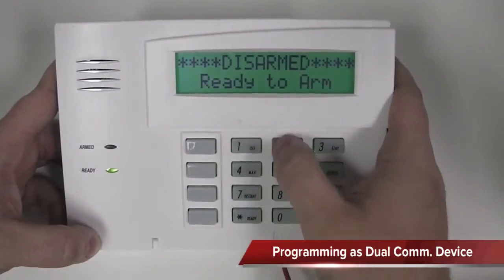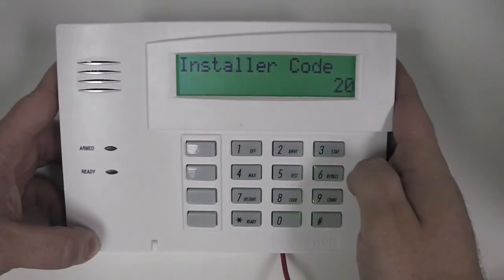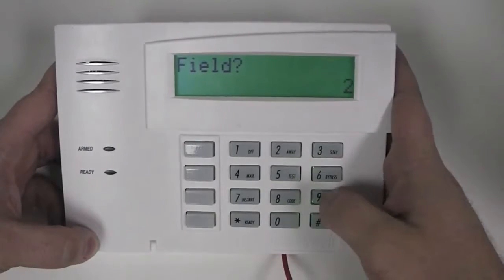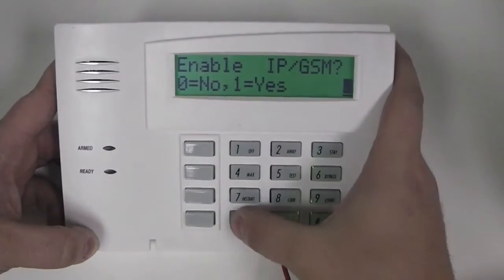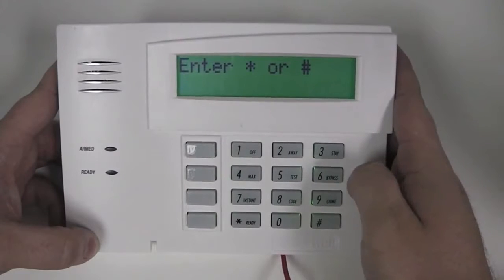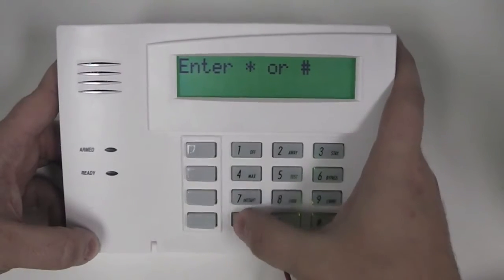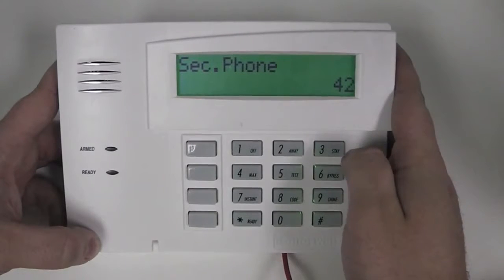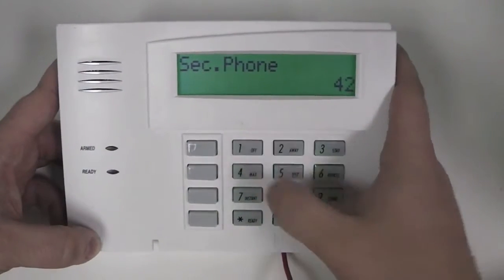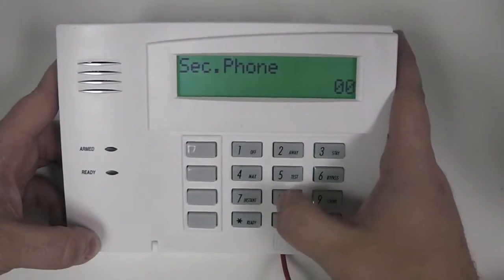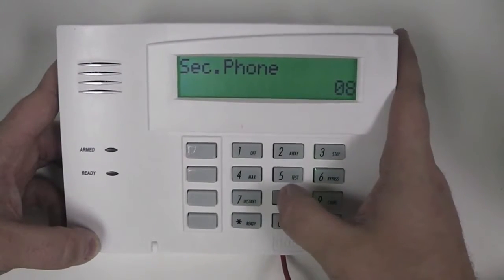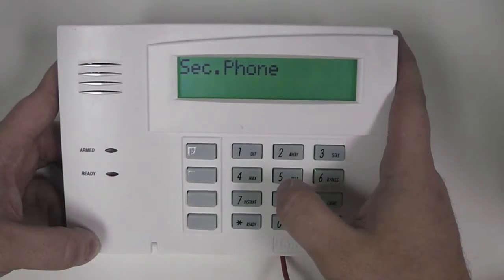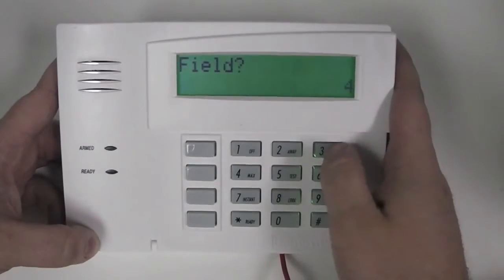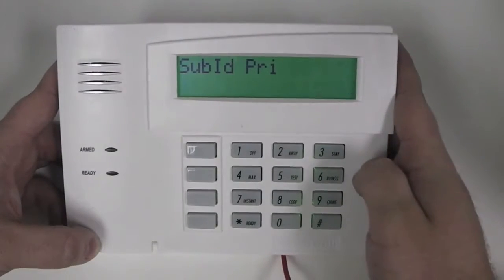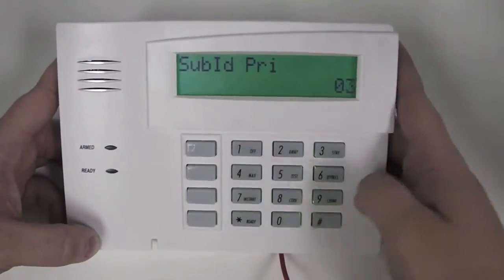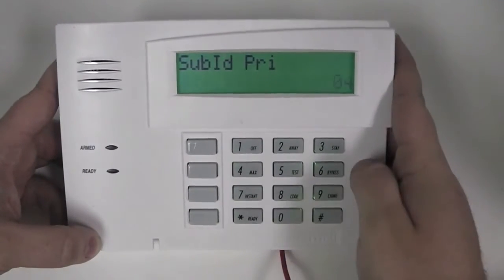The last way to program the BAT is as a dual communicator. You start off by entering programming again, and then verify that *29 is enabled. To enable it, you just hit *29, press 1, and then **. Next, we'll move on to 42. Again, make sure that the phone number is entered in. Verify whether you have to put in the 1 in front of the phone number. Once you're done with the phone number, you hit *. Verify that the account number is still in. You can press #43. If it's not, you hit *43 and enter your account number, followed by *.